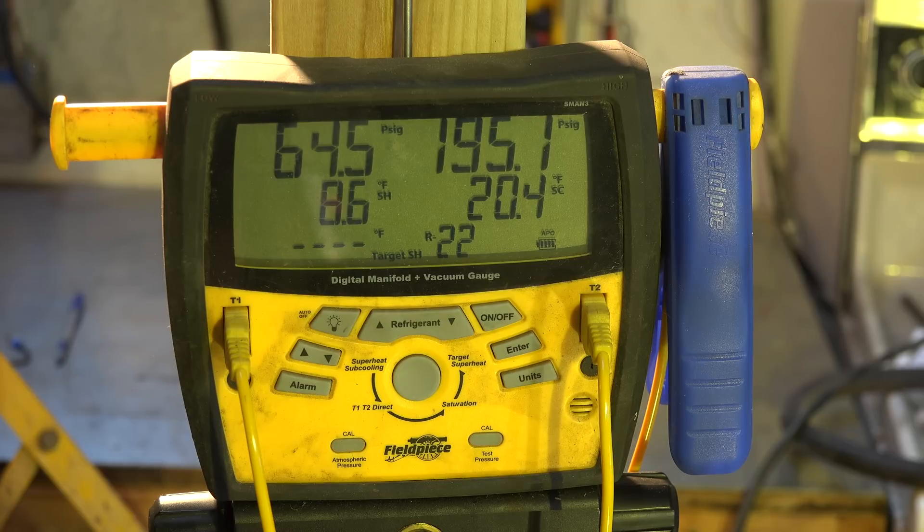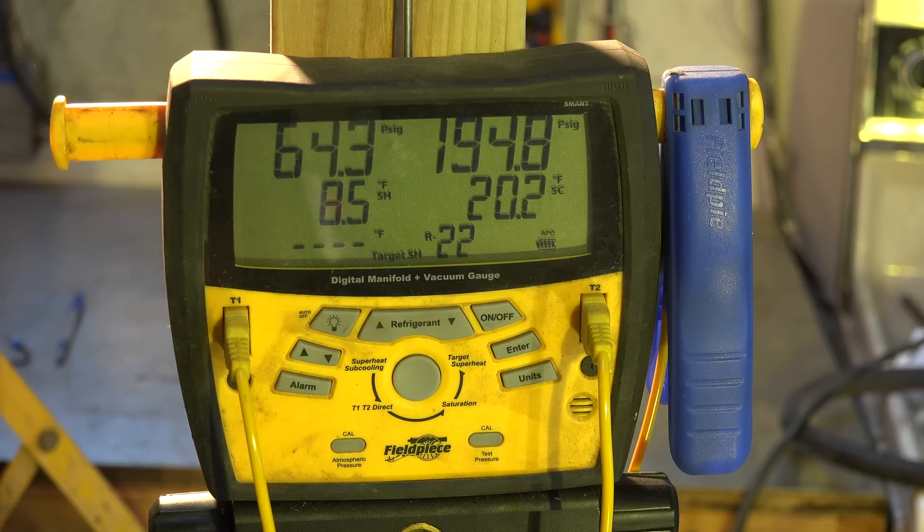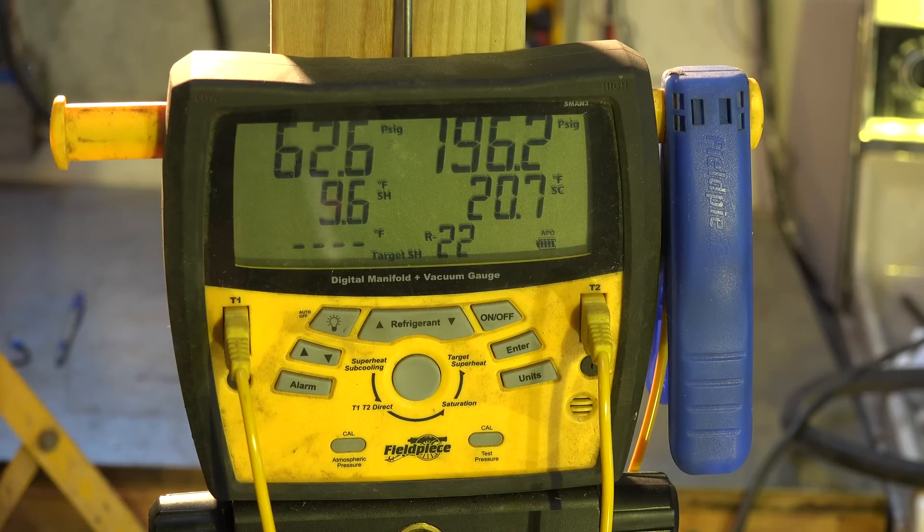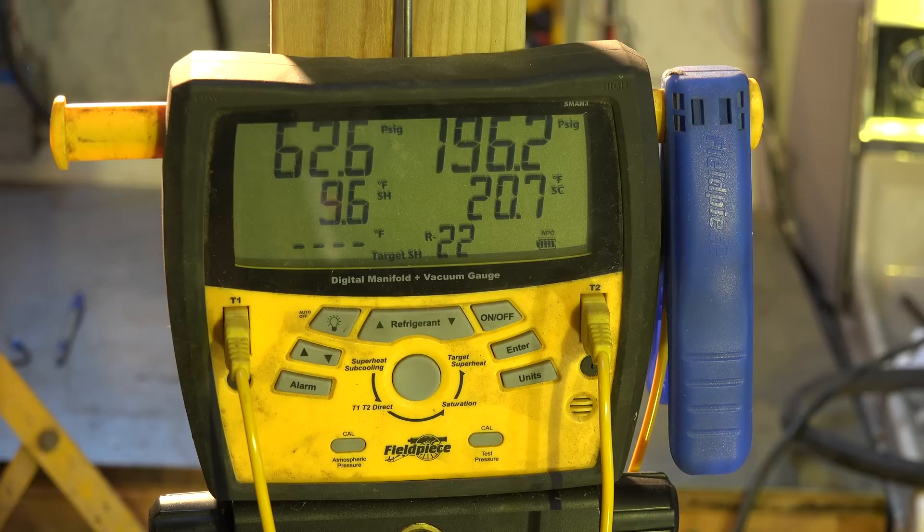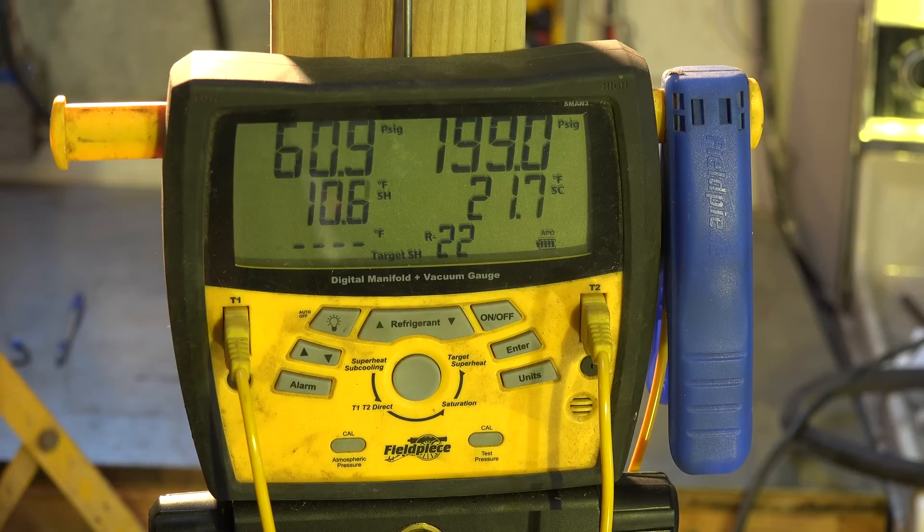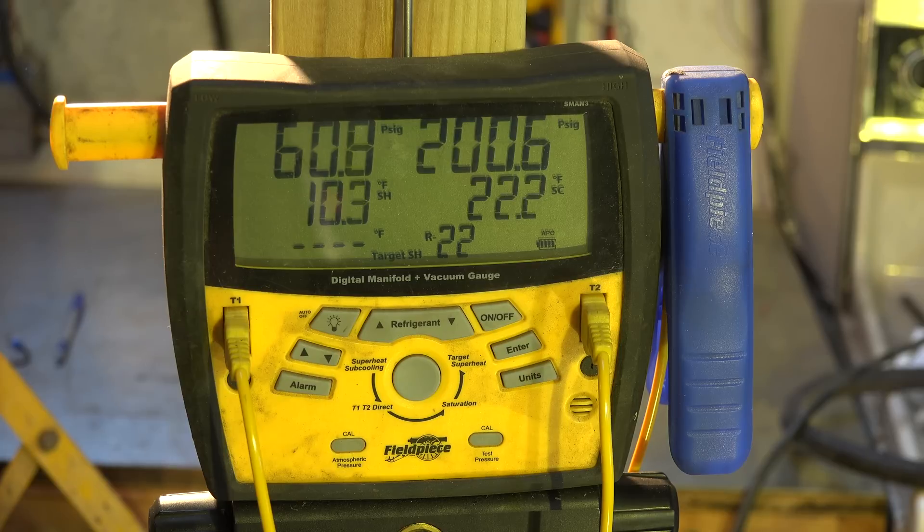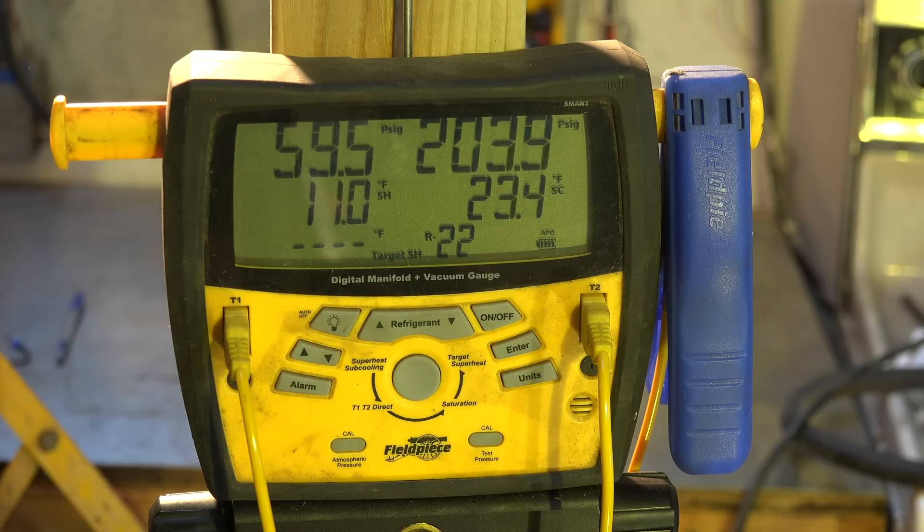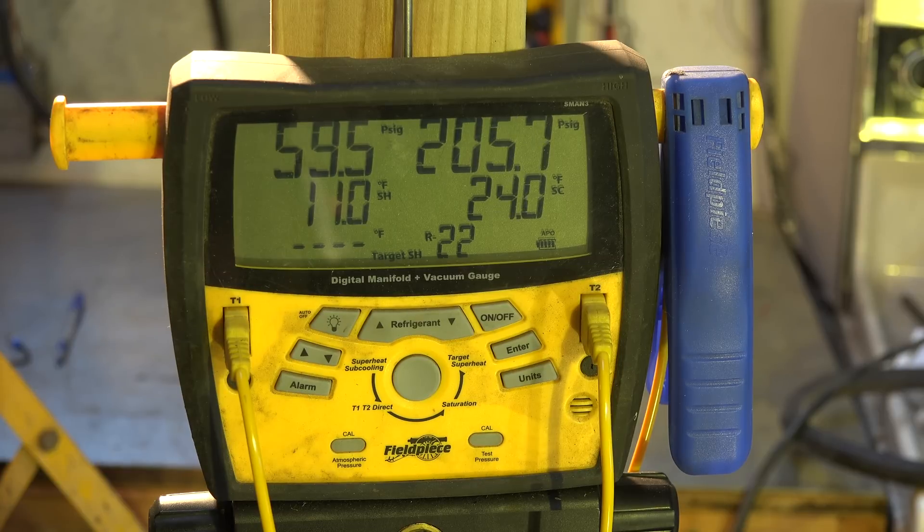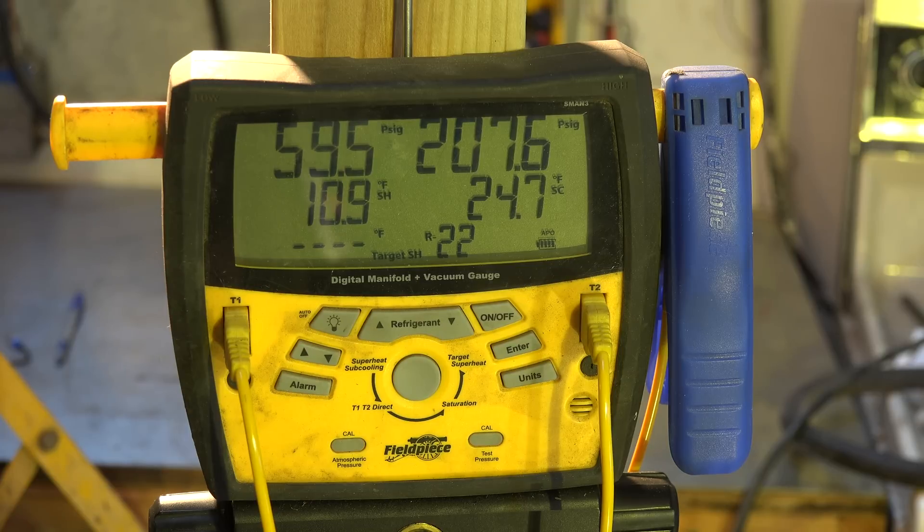Now we're back to where we should start the fan again. Superheat's about 8.4. You can see that kind of lag we have there. We're up to 11 and we've been as low as 8.4. What happens with these things is the superheat changes as the fan cycles on and off because of the pressure difference.